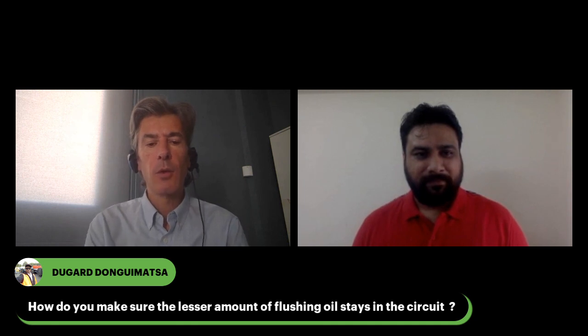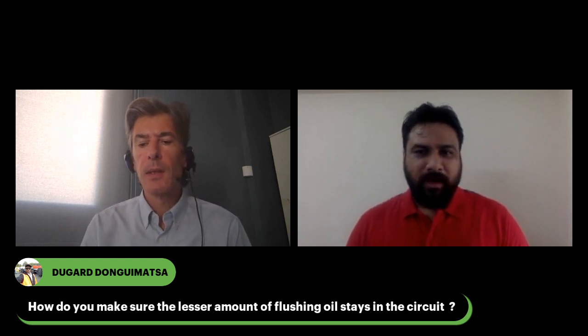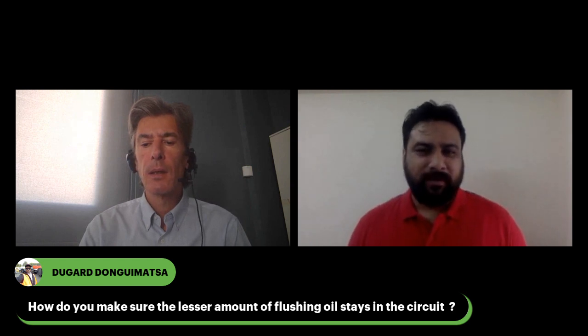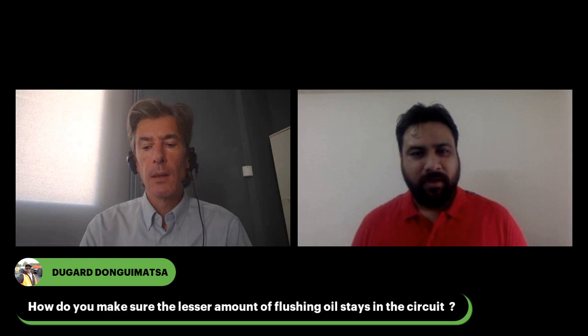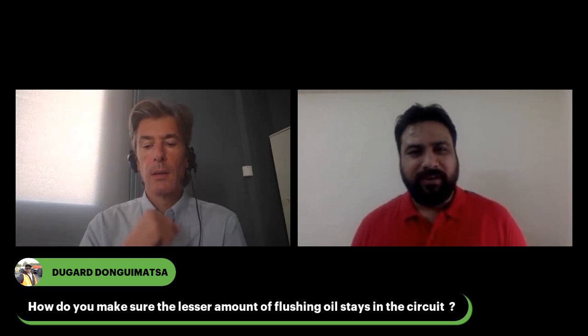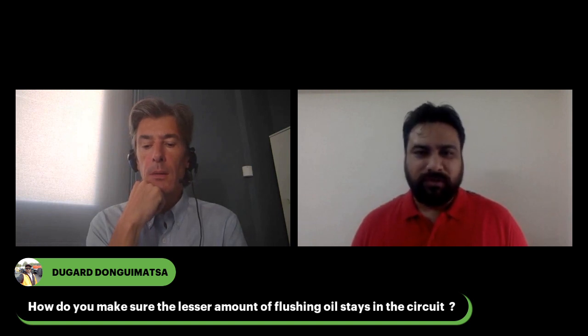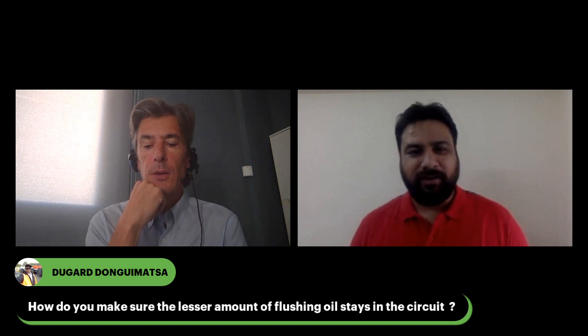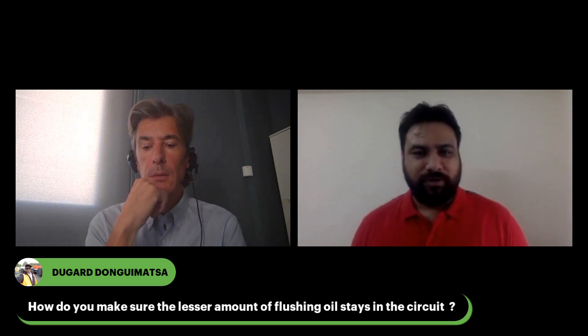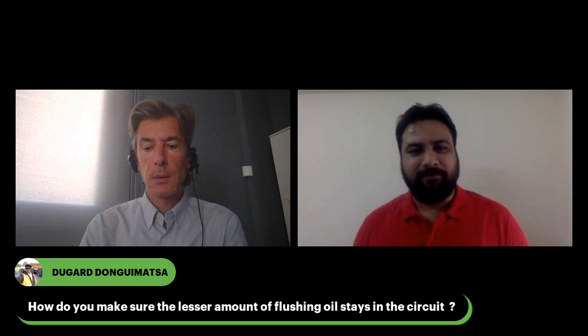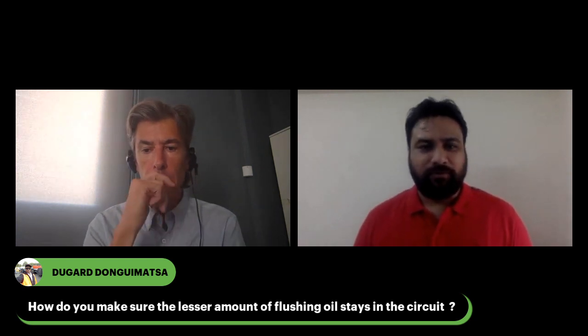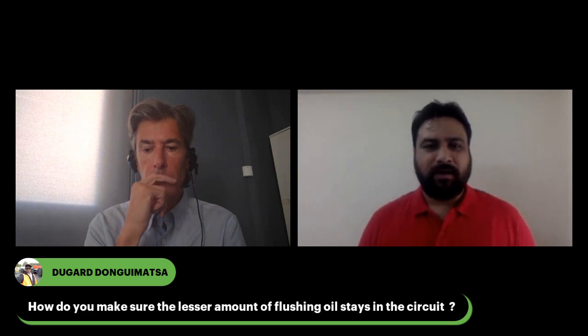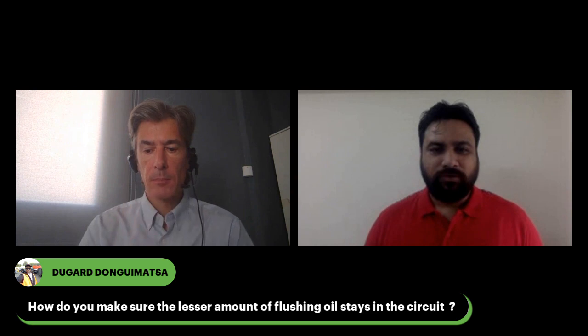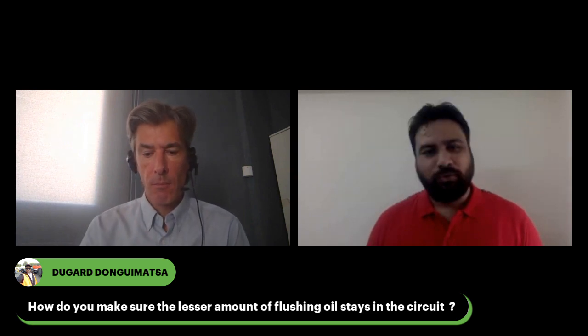The question was regarding the quantity of flushing oil used - how do you keep it in the circuit if it's a lesser quantity? I believe what he wants to say is the stagnant flushing oil which would remain in the system once you have concluded the flushing. For that, you would need some nitrogen purging devices, and you could use some ports on the flushing loop. With that, you can purge high pressure nitrogen into the system, and that would solve the problem. While doing this, it's important to take care of the nitrogen you are pouring inside the system, because that should not hamper the entire flushing activity. But the first point was more relevant here - you use flushing oil that is compatible with the lube oil system, so that even if flushing oil remains in the system, you don't have to worry about it.